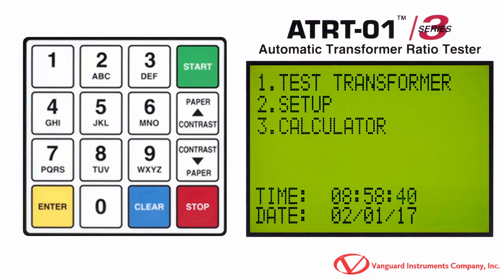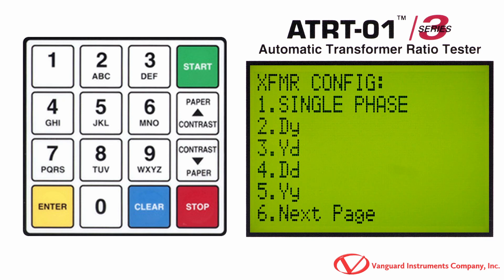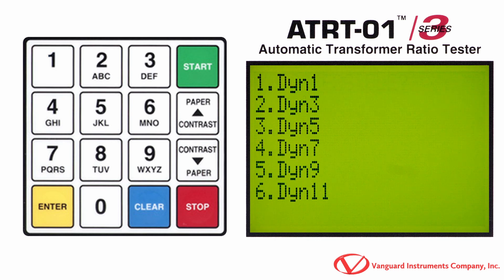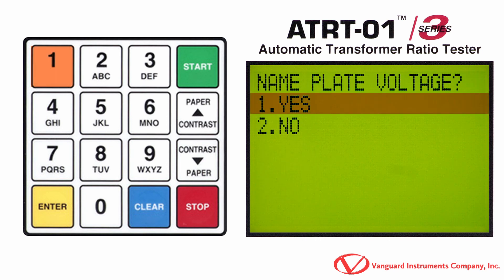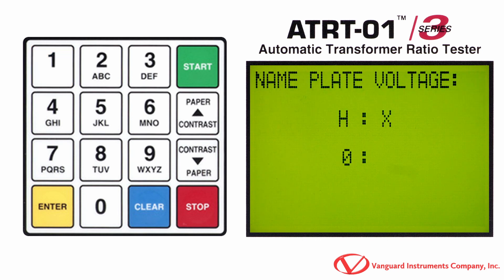To start performing a three-phase test, we'll press the 1 key to select Test Transformer from the main menu. For this example, we are testing a delta-to-Y type transformer, so we'll press the 2 key. The X0 terminal is accessible on our transformer, so we'll press the 1 key. Our transformer is a DYN1 type transformer, so we'll press the 1 key. Now we'll press the 1 key to enter the nameplate voltages for our transformer.